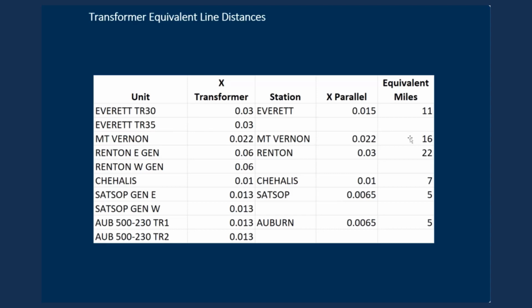For Mount Vernon, we have 16 miles. For Renton, we have two parallel generators, each with impedance of 0.06, and that's equivalent to 22 miles. For Chehalis, which is a large unit, it's 0.01, the reactance, and that's 7 miles. And for Satsop, which are very large 1200 megawatt units, we have two very large generator step-up transformers, each of 0.013, and that combines to 5 equivalent miles. And we've got our bulk power transformers at Auburn that give us 5 equivalent miles. So depending upon where our capacitor is located, we'll be looking at various generating combinations as the supporting generators for that bus, and you'll have to include various amounts of their generator step-up reactance.